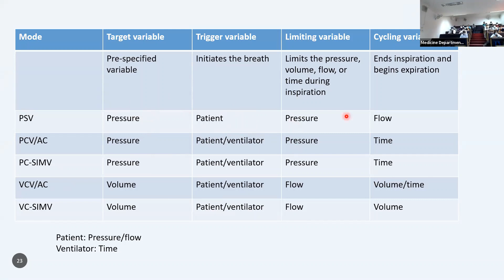As I said, the fourth thing, setting alarms is really important, and setting appropriate alarms is also very important. So in this pneumo vent, we have got pressure limits. You must set appropriate pressure limits. In this case, the pressure limits probably are not set right. Similarly, in PCV mode, you should set a pressure alarm setting of minimum minute ventilation. So if the minute ventilation goes down a particular value, the alarm may ring. In volume control mode, the higher pressure limits are quite important.